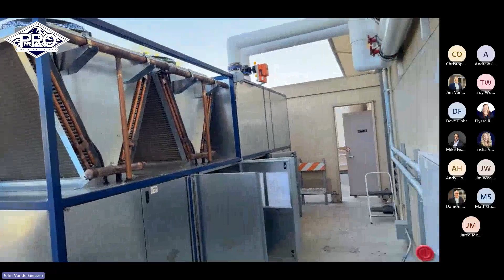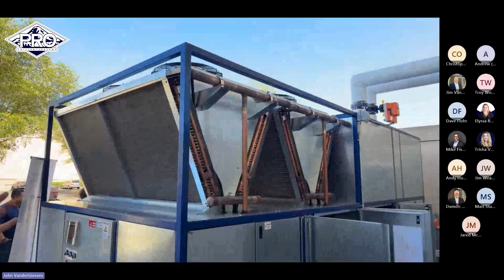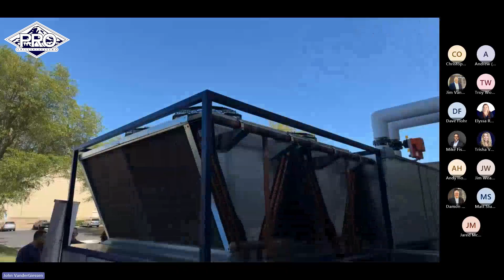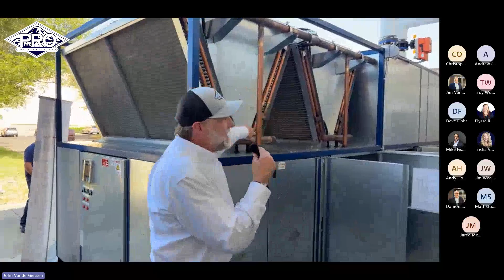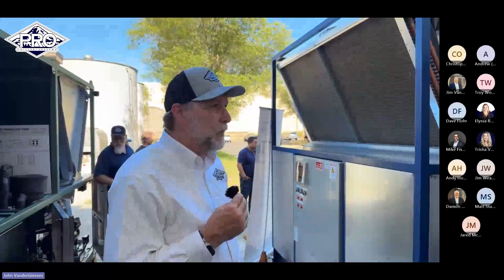The difference between this system and the other one is that this one operates with CO2 as a refrigerant, while the other has the newest A2L refrigerant, R454C. Same components - we have our refrigeration, closed refrigeration circuit, our fluid, our backup pumps. What you won't see on this system is heat recovery - there is none. All the heat that comes off of our system is discharged into the air, simply because the temperature isn't hot enough to effectively recover that waste heat. Unlike the CO2 system, where we can heat water up to 180 degrees.